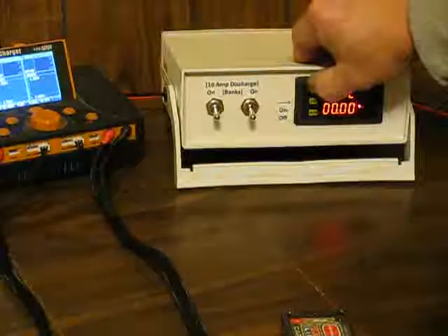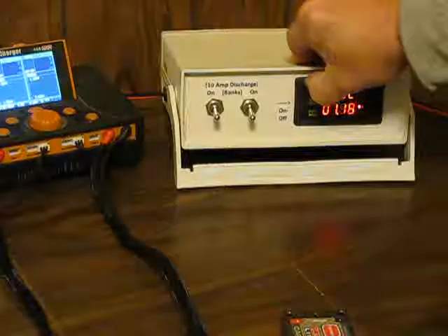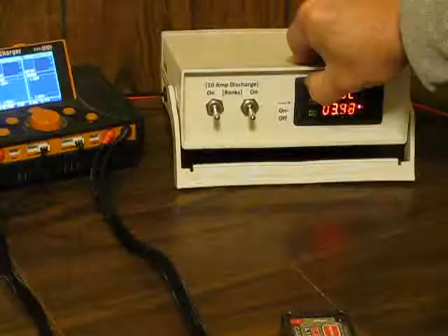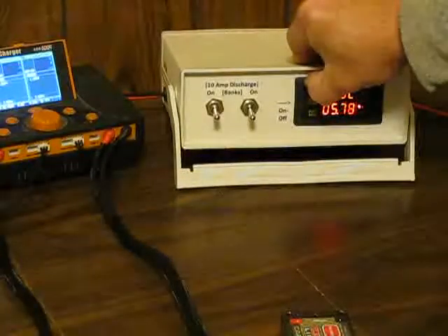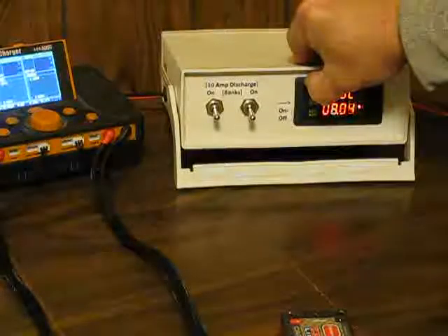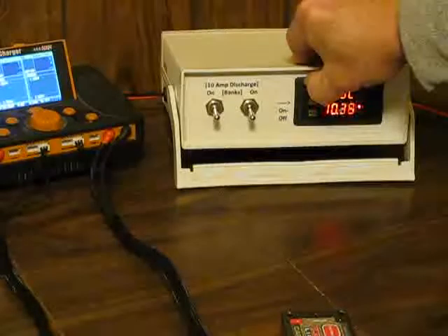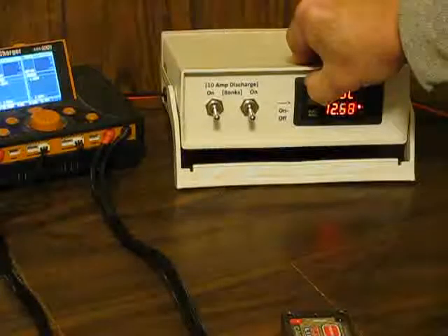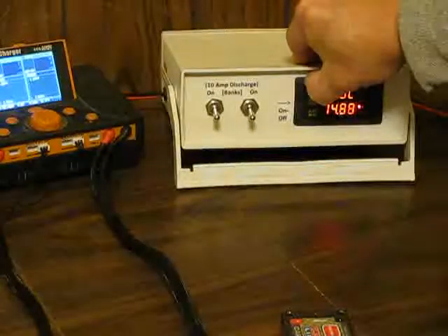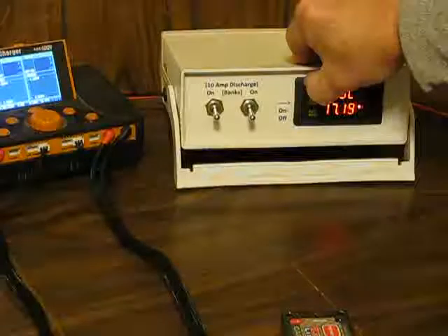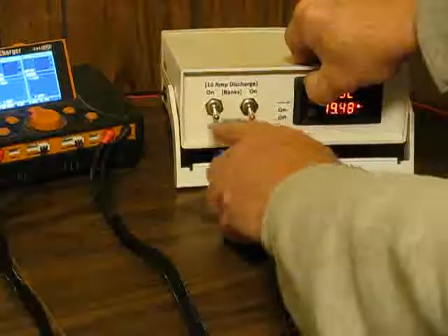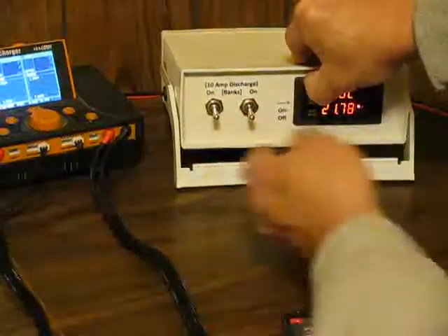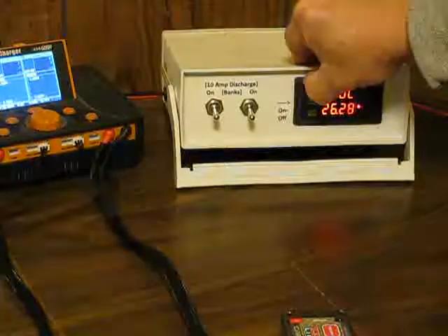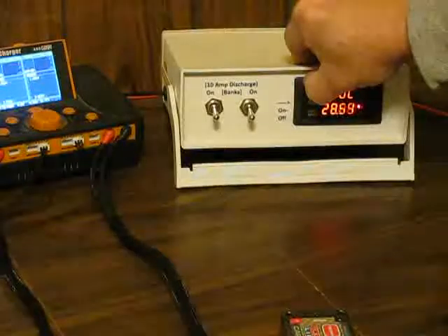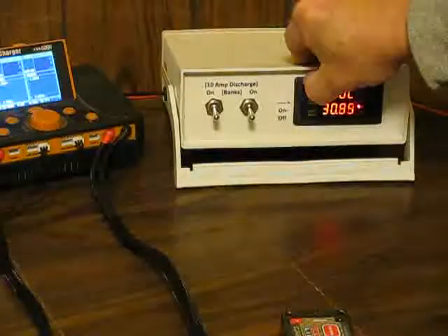We'll do the same thing, holding the button down. When you plug in a full battery, this unit draws a little over 37 amps from the battery at 8 volts. At 7 volts it's down to about a little under 33 amps with both banks turned on. With both off, it's 15 amps; click one on, it's 25 amps; click the other on, it's 35 amps. You can use either one to get 25 amps.